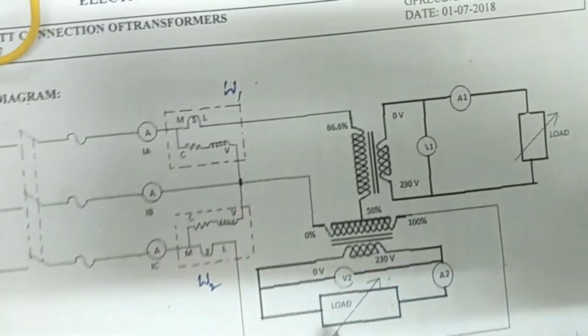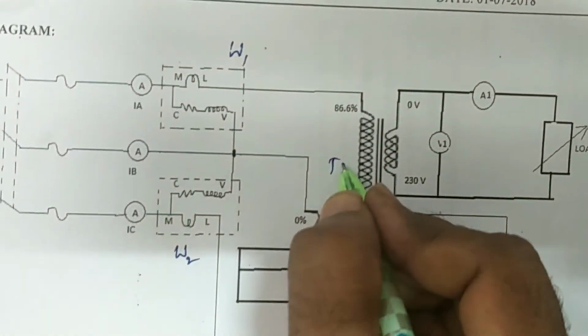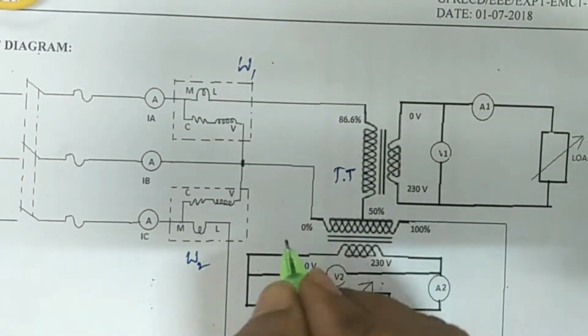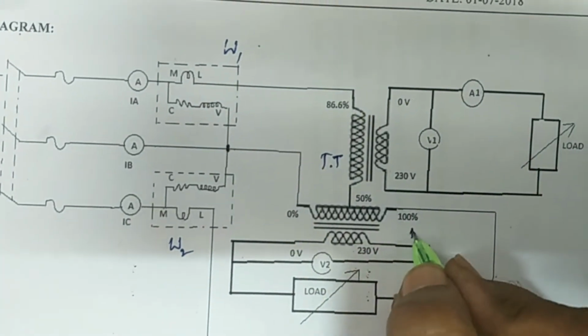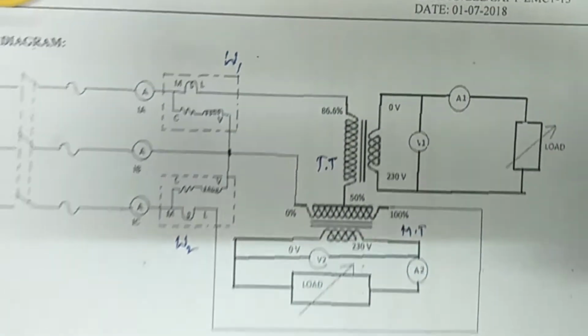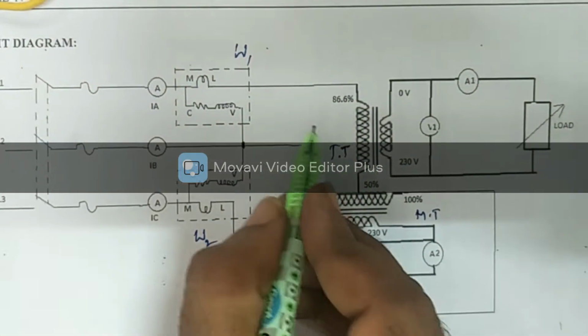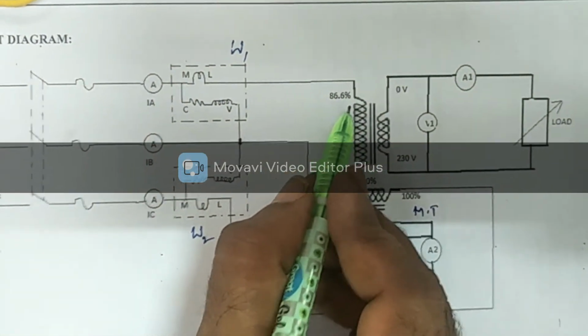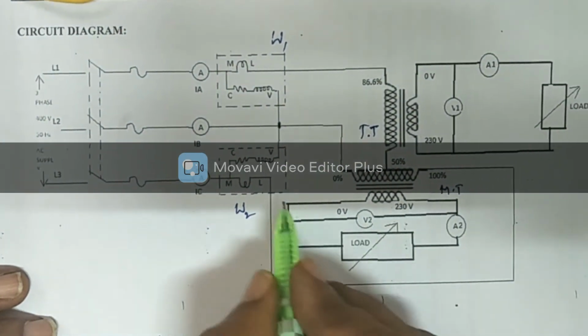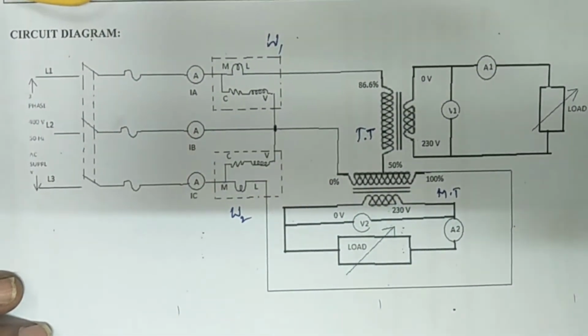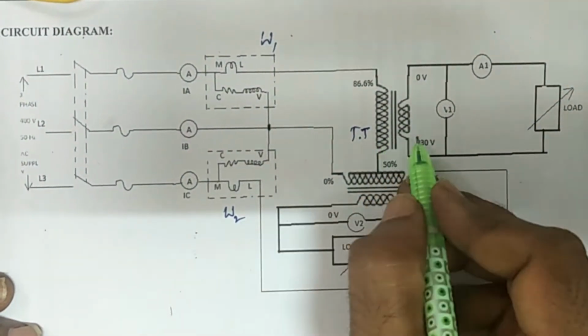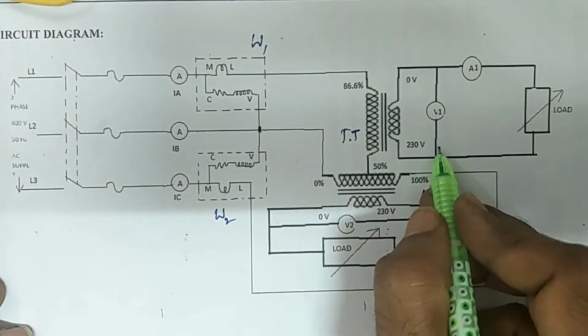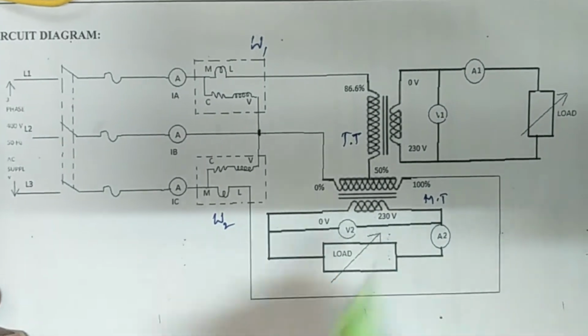And there are two transformers here. This is the teaser transformer, for the present I am calling it TT, and this one is the main transformer, MT. For the teaser transformer you are going to consider only 86.6% of the turns, and for the main transformer you are going to take 100% of the turns on both sides. For the teaser transformer the secondary is this one, and the main transformer secondary is this one.